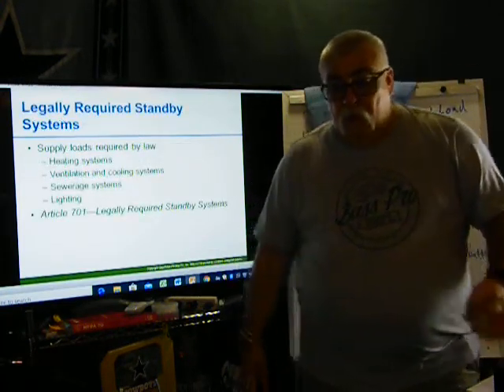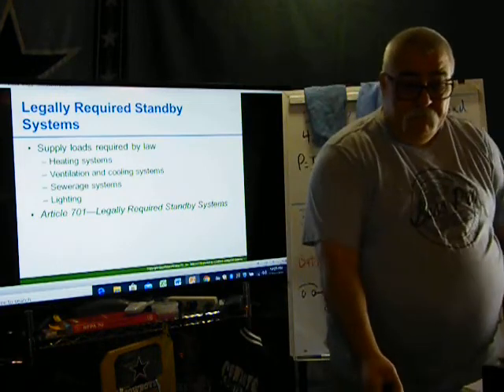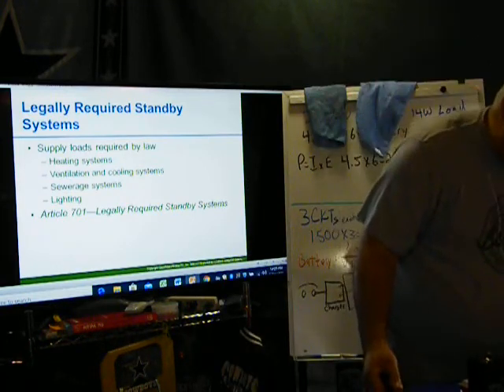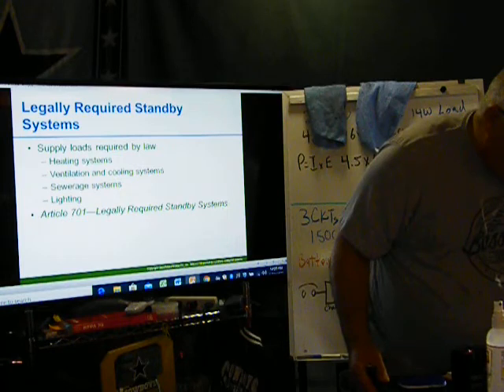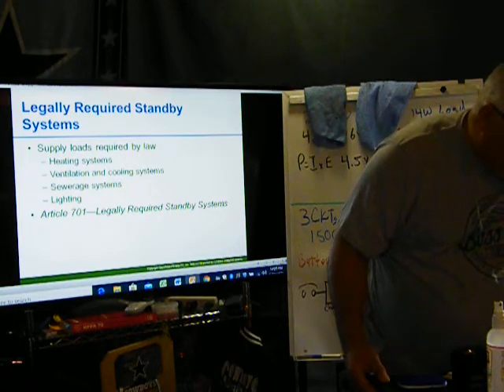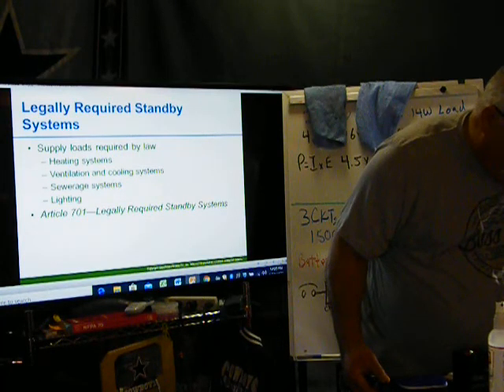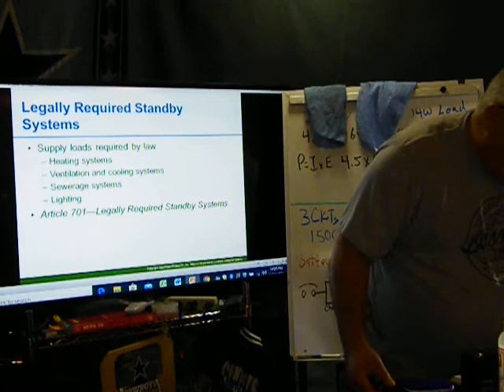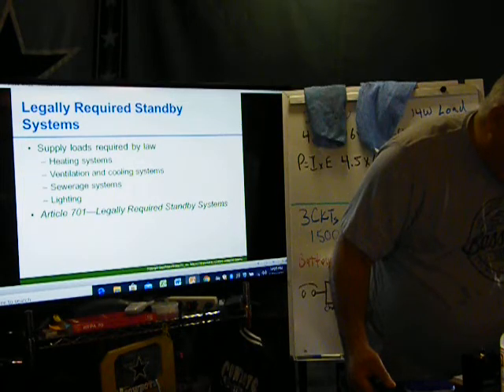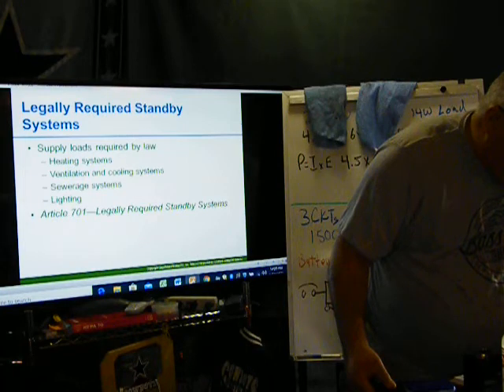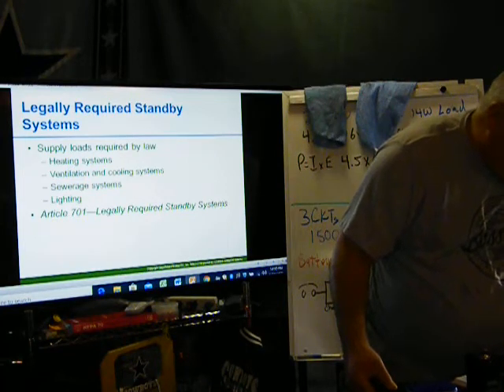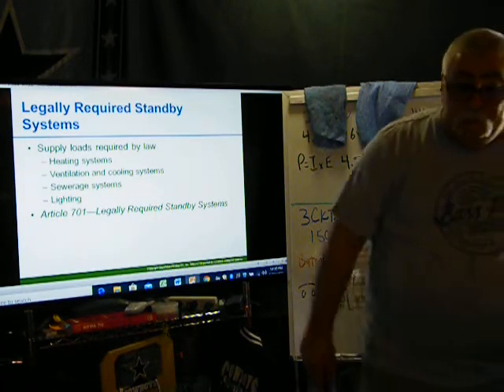Legally required systems. So legally required standby systems, as the name suggests, are emergency systems supplying loads required by law in the event of a normal power loss. The loads supplied by the legally required standby system could create hazards or hamper rescue and firefighting operations when normal power is interrupted. Some loads that may be supplied by the system include the following.